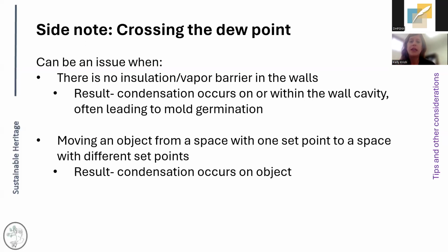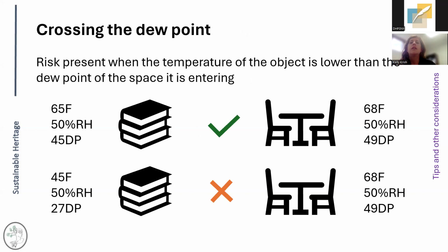It can also be an issue when there's no insulation or vapor barriers in the wall and we cross the dew point within the wall. That means condensation is occurring within the wall and can lead to mold germination. So what this essentially means is if the temperature of the object is lower than the dew point of the space it's entering, you have a risk of condensation. Think back to that glass again. You don't want your object to be that glass with the water on it.